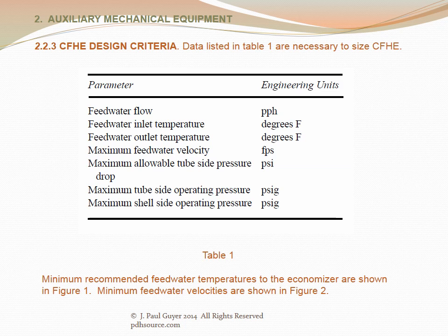Data listed in table one are necessary to size the CFHE. These include feed water flow, feed water inlet temperature, feed water outlet temperature, maximum feed water velocity, maximum allowable tube side pressure drop, maximum tube side operating pressure, and maximum shell side operating pressure. Minimum recommended feed water temperatures to the economizer are indicated in Figure 1, and minimum feed water velocities are shown in Figure 2. Each CFHE will be a U-tube type heater to minimize stresses caused by thermal expansion; tubes of stainless steel construction will minimize corrosion and erosion.